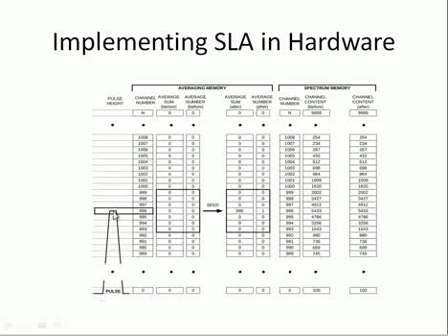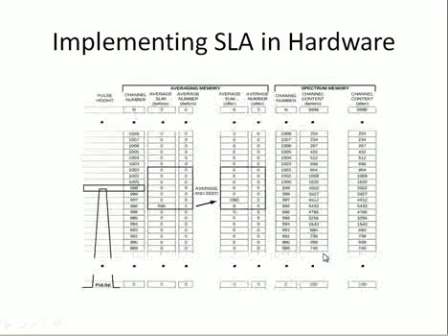So imagine that the first pulse height that we measure comes here at channel number 996. And when that pulse height comes in, we're going to look to see if there are any averaging windows that are close to that pulse height that we need to average the pulse height with. But there aren't any in this particular case. And so we're going to start a new averaging window. Since they were all zeros, that means there were no averaging windows here. And so we're going to start one by putting in the pulse height that we measured and a count of how many pulse heights, which is just 1 so far.